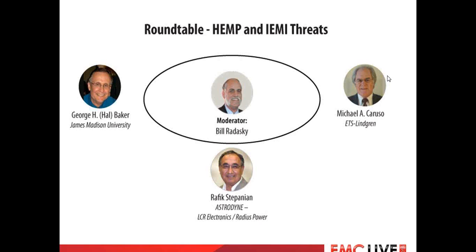The basic protection starts with a six-sided shielded enclosure, constructed from ferrous material so you can address the magnetic component as well as the electric and plane wave. You also have to pay very close attention to all points of entry - for communications, electric power, heating, ventilating and cooling, fire protection, fresh water, wastewater. In some facilities that can get quite large, the entire protection system gets quite complicated. And let's not forget that grounding of these facilities is absolutely critical - we need multi-point grounds that are able to carry the load.